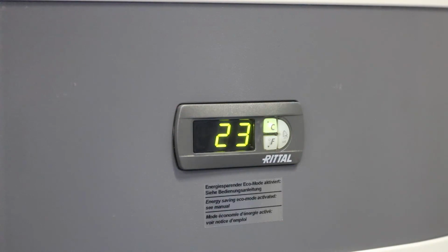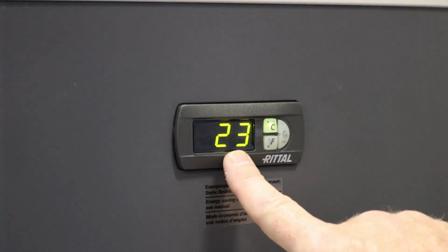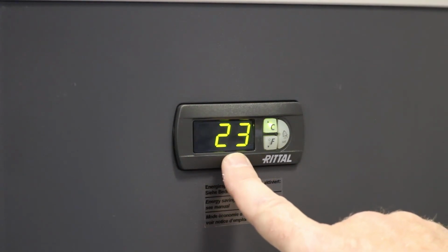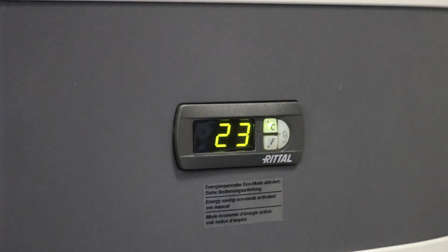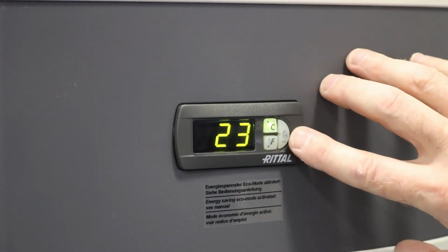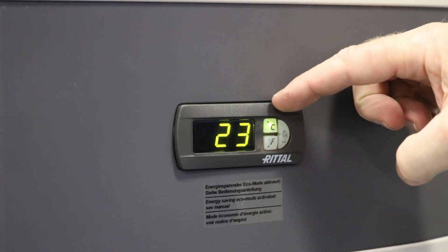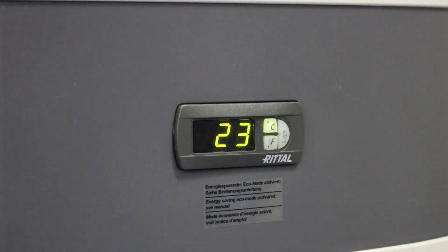Okay, so I'm here at the air conditioner. You can see my display right here, and the first thing you want to do is make sure that the unit is actively cooling. This will also engage the sensors, which will establish the baseline temperature from this point. My comfort controller is showing 23 degrees C internal temperature, and since it's steady, there are no alarms, no warnings. On the keypad, I've got a set key, a Celsius button and a Fahrenheit button, and I use those to program my comfort controller.